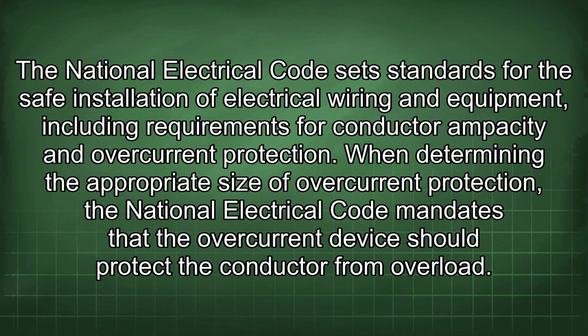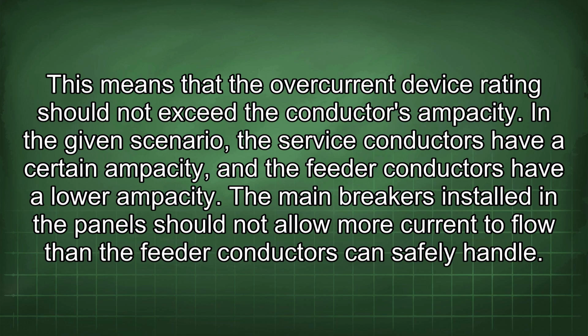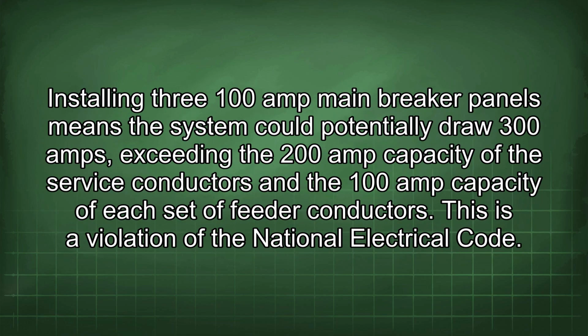and overcurrent protection. When determining the appropriate size of overcurrent protection, the National Electrical Code mandates that the overcurrent device should protect the conductor from overload. This means that the overcurrent device rating should not exceed the conductor's ampacity. In the given scenario, the service conductors have a certain ampacity, and the feeder conductors have a lower ampacity. The main breakers installed in the panel should not allow more current to flow than the feeder conductors can safely handle. Installing 3 100 amp main breaker panels means the system could potentially draw 300 amps, exceeding the 200 amp capacity of the service conductors and the 100 amp capacity of each set of feeder conductors. This is a violation of the National Electrical Code.